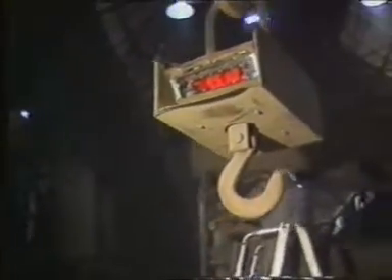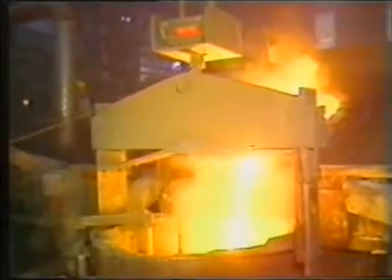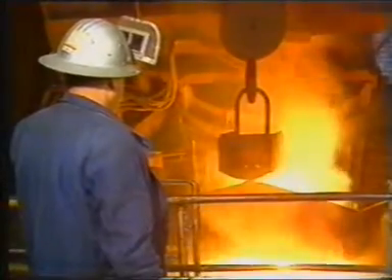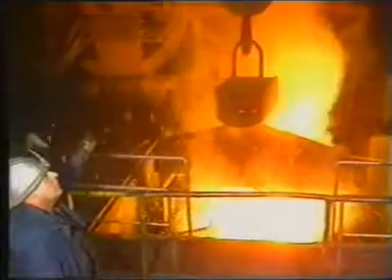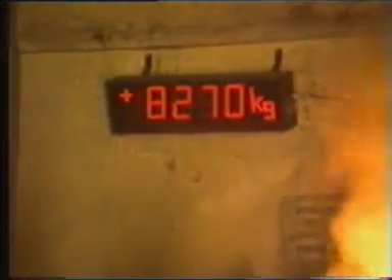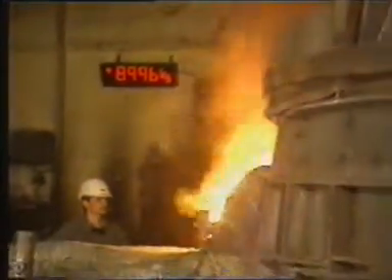This 30-ton version is doing its job next to molten metal at a temperature of approximately 1400 degrees Celsius. Thanks to its zero-fault casting record, this investment in an EHP scale has paid for itself many times over. Its reliability in measuring all alloy additives accurately and repeatedly ensures the highest quality and economic production. Weighing data can also be transmitted by UHF radio signals to an additional digital display.